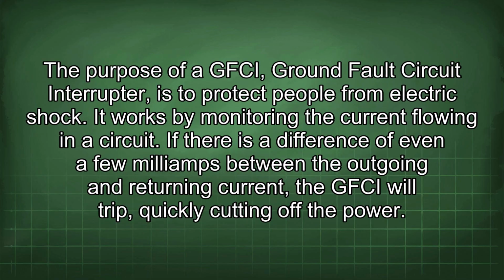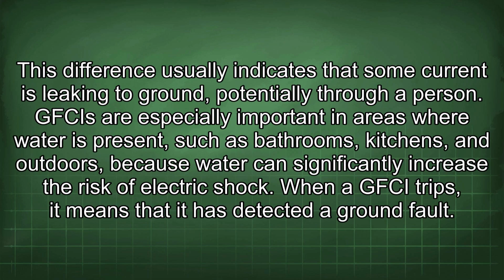The purpose of a GFCI, ground fault circuit interrupter, is to protect people from electric shock. It works by monitoring the current flowing in a circuit. If there is a difference of even a few milliamps between the outgoing and returning current, the GFCI will trip, quickly cutting off the power. This difference usually indicates that some current is leaking to ground, potentially through a person.